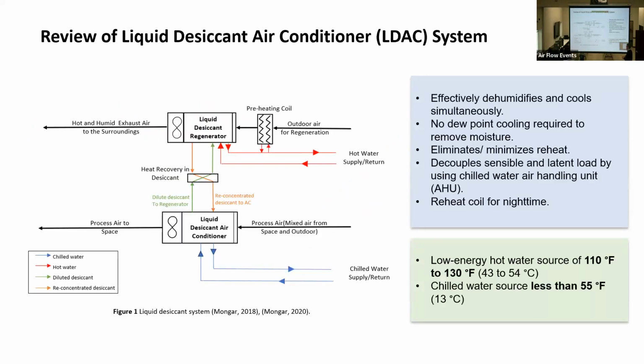In the paper that we have here, this is our system for this cannabis facility in Pennsylvania. We have our liquid desiccant air conditioner. So we're taking return air from the room. We are cooling and dehumidifying. Alongside, we have a chilled water air handler so that if the air is at the proper humidity conditions, that will divert the chilled water over to the air handler. And the air handler has circulation air requirements, so that's continuously running.